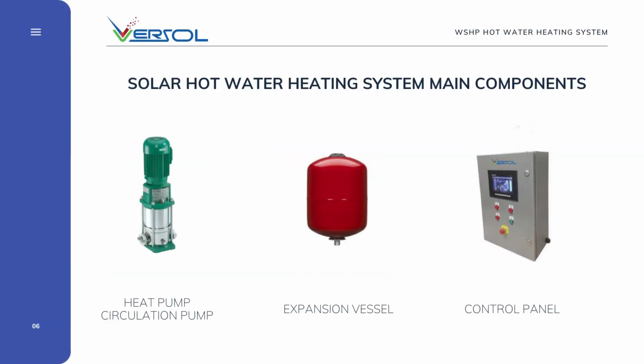As a system provider, our specially trained design team can suggest other main components like the circulation pump, expansion vessel and other safety devices for the smooth operation of the system. The circulation pump shall be selected to ensure its suitability for high temperature application. The expansion vessel shall be sized and selected based on the water expansion volume, operation temperature and system pressure.